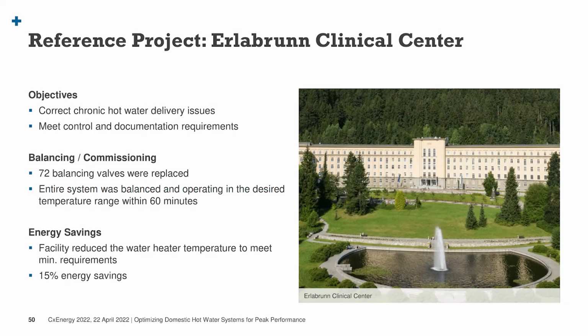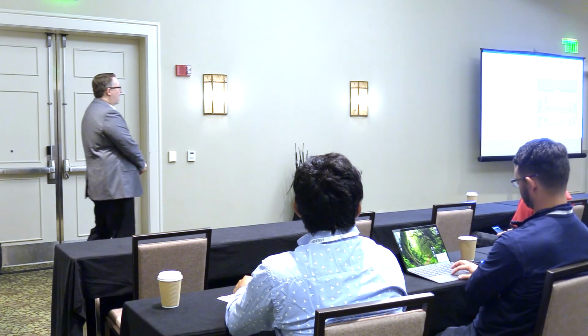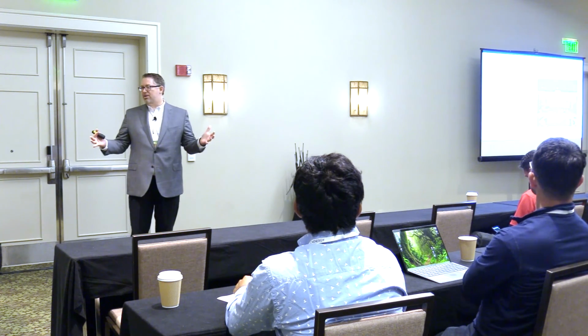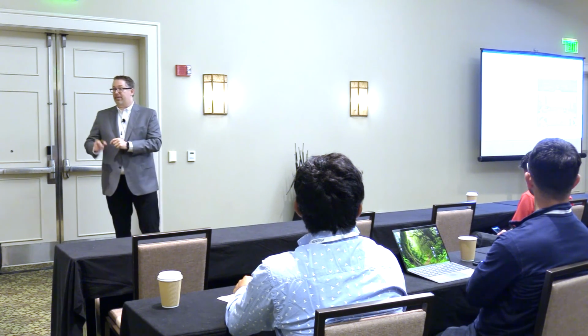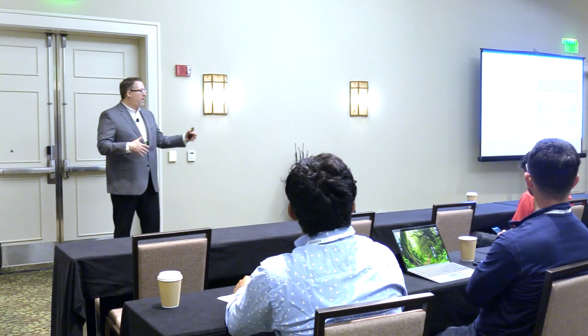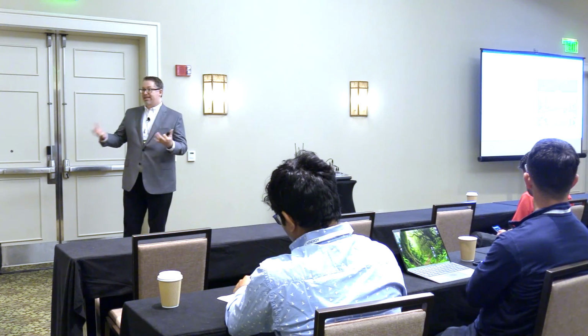Here's one of the reference projects, one of the very first with an automation system. This was an existing hospital that over the years had multiple renovations and additions—hospitals are constantly doing some type of work, moving patient rooms and operational spaces around. This one had experienced significant changes over the years and had chronic hot water issues because they never had a commissioning agent or a TAB agent come out to review what the impact would be on their system as they did these additions. This particular reference study was done in Germany, where they had national control and documentation requirements—they had to store at a certain temperature, deliver at a certain temperature, return at a certain temperature, and be able to prove they were doing that.